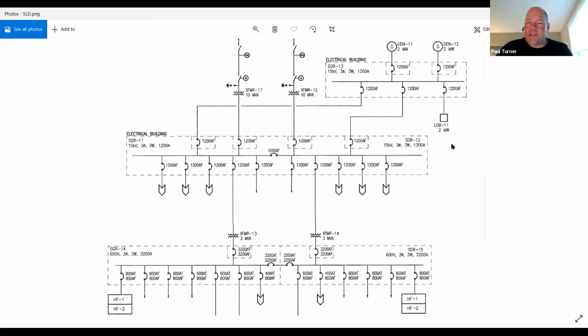Okay, so I was discussing the static load, the 2 megawatt static load here. Typically, the gensets don't run very often. Ideally, they never run, but you do want to verify that they are capable to run when needed. So periodically, monthly, weekly, whatever your maintenance schedule determines, we can connect each genset to the 2 megawatt static load and run it for a period of time at full load to confirm that the genset is ready to run when it's required.